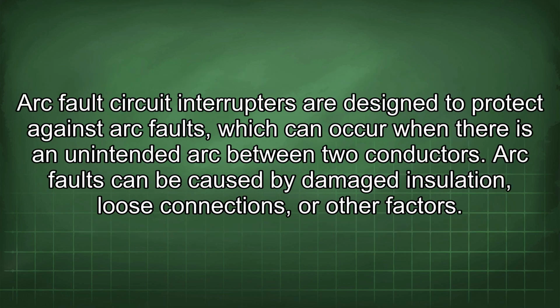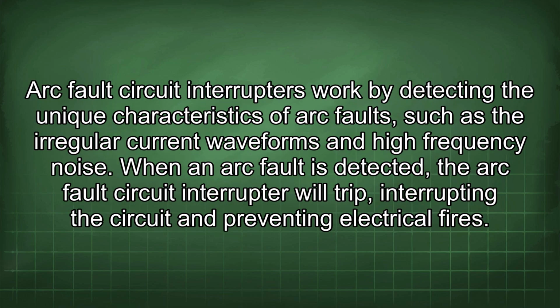Arc fault circuit interrupters are designed to protect against arc faults, which can occur when there is an unintended arc between two conductors. Arc faults can be caused by damaged insulation, loose connections, or other factors. Arc fault circuit interrupters work by detecting the unique characteristics of arc faults, such as the irregular current waveforms and high-frequency noise.